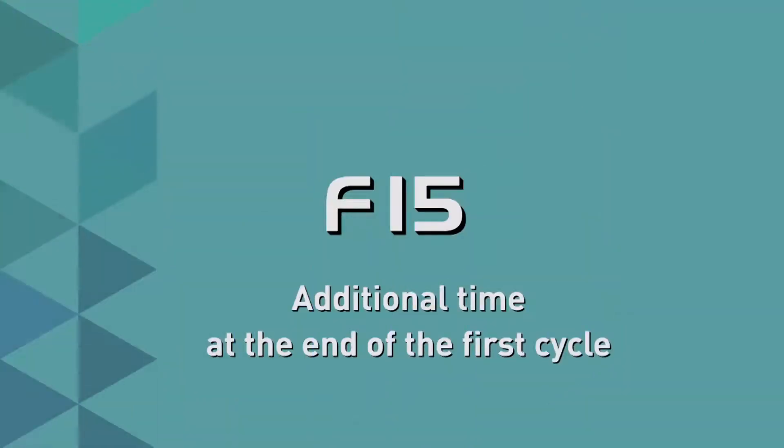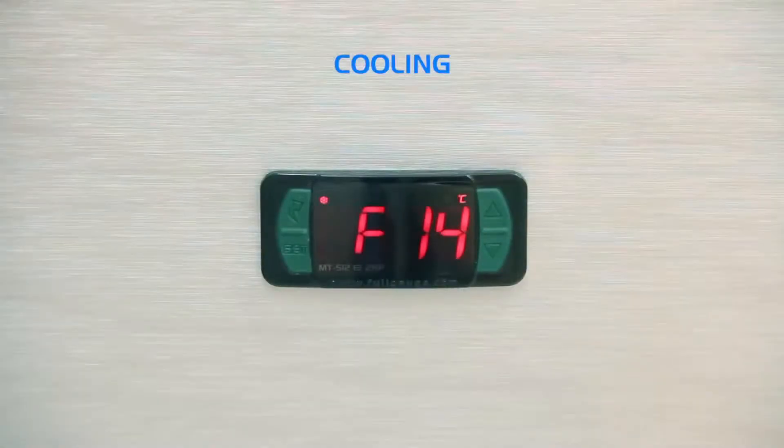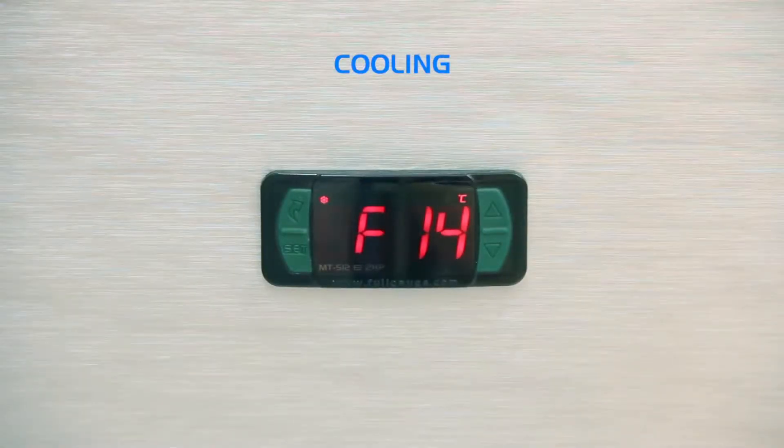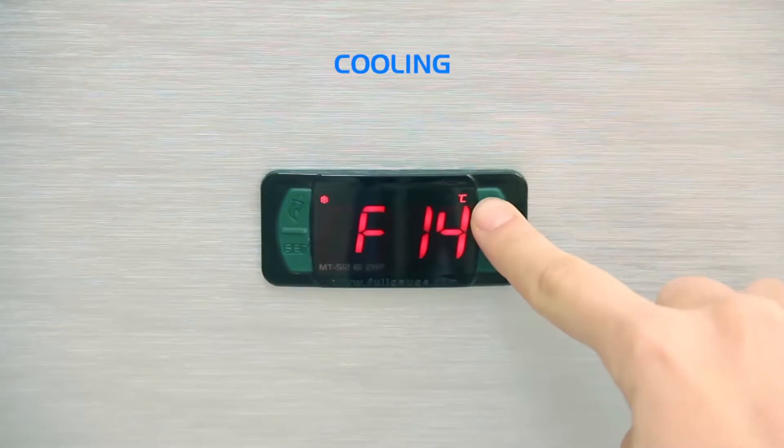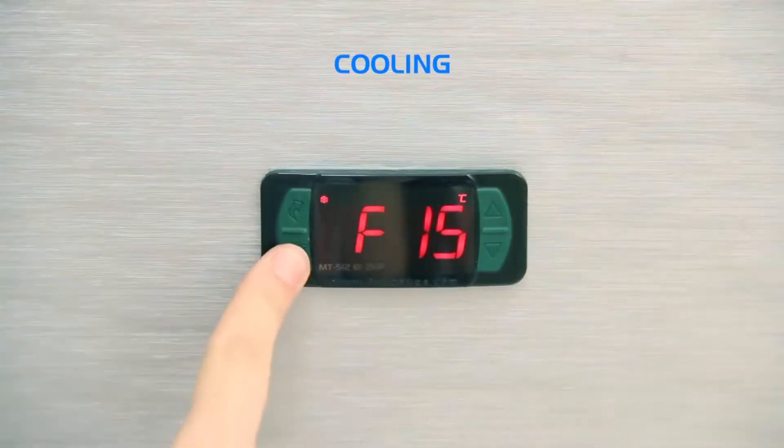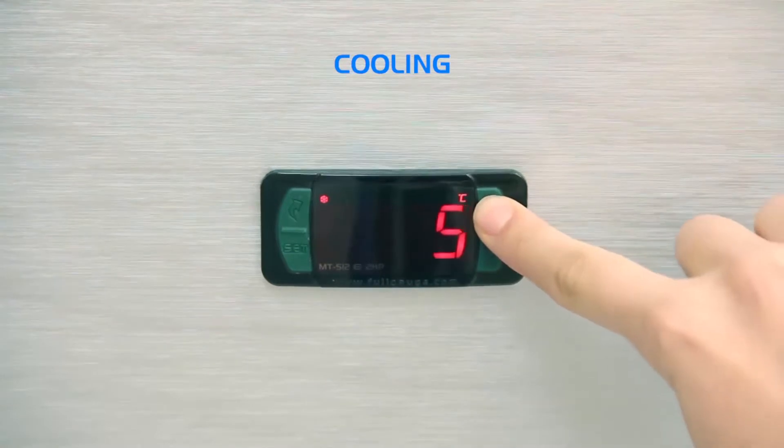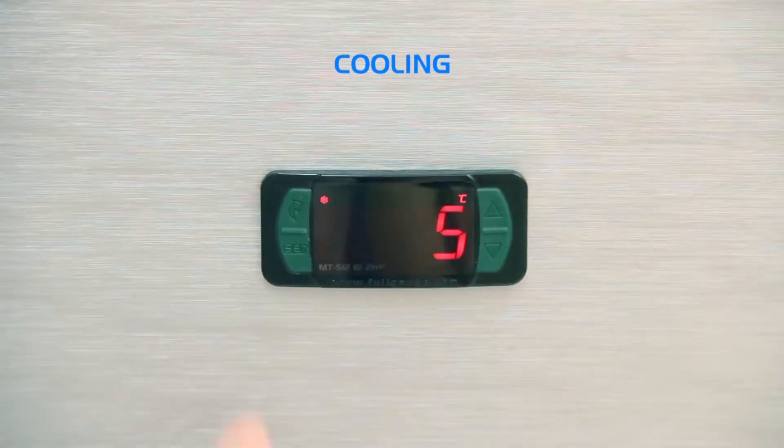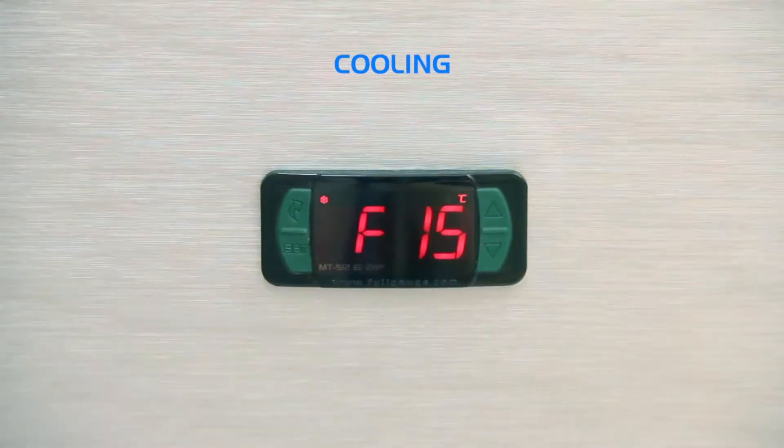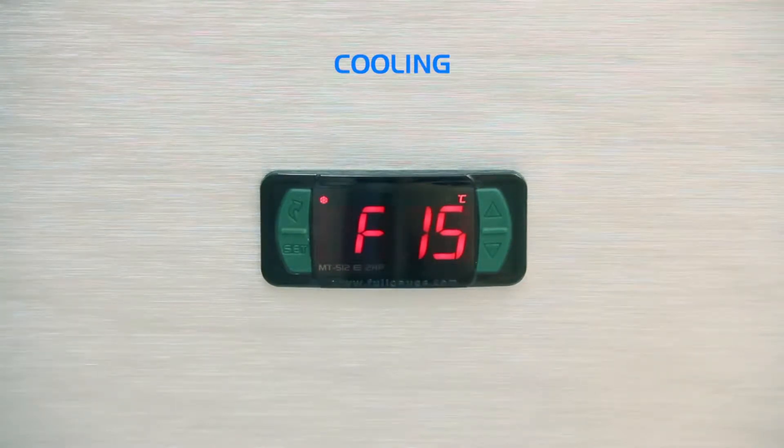F15 Additional Time at the End of the First Cycle: This parameter allows you to increase the cooling time of the first cycle after driving the controller. If you do not wish to adopt an additional time, select No, or provide a time of 1 to 240 minutes. In the example, we opted for an increase of 5 minutes.